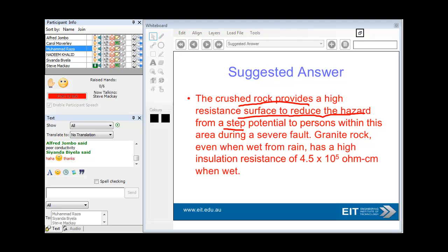Step potential is the potential across your steps, across your feet. There are two types of potential: step and touch potential. We're worried about step potential at the substation, which has granite rock, which even when wet has a very high insulation resistance of 4.5 times 10 to the 5 ohm-centimeters. So even when wet, it's very high resistance, meaning that if you touch something, you're still okay in that substation.